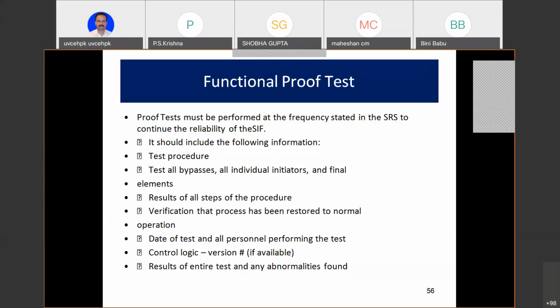Thank you. One question I have, sir. Yeah, please. What is a proof test interval? Okay, very good question. I like that because it is a sharp question. Now, for example, you have a critical plant like the hypothetical plant that I showed you. There, as per international rules and standards, the proof testing for that pressure switch, which you saw 3 of them, is, let us say, once in 3 months. So the interval is, suppose you do it today, 3 months later you have another chance to check it. And what you do in proof testing, you get permission from the control room and take a permit, and at that time it is bypassed with permission, and you don't take it to the laboratory. You do it there by simulation sometimes, but you do something else also.